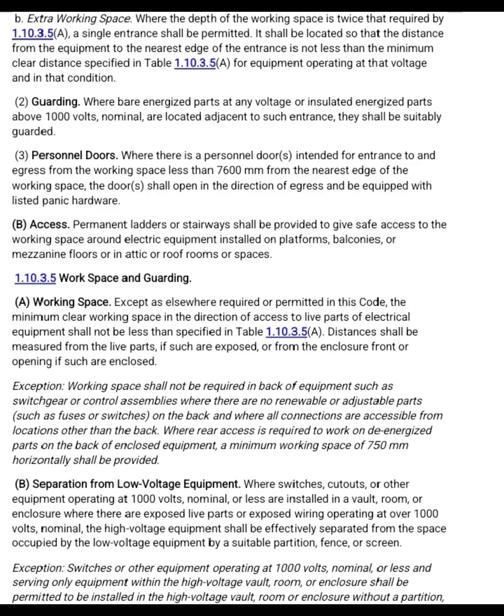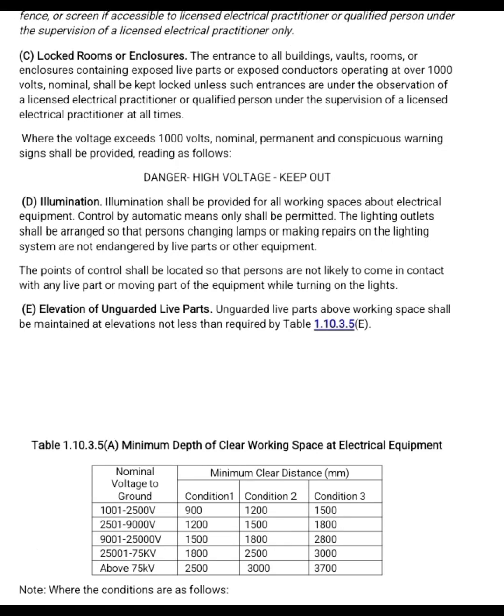This indicates that for extra working space, if the working space is twice the nominal depth, you are allowed to have only one entrance. And in guarding your entrance, if there are bare live parts or insulated live parts above 1000 volts near an entrance, they must be guarded to prevent accidental contact. C. Locked rooms or enclosures. The entrance to all buildings, vaults, rooms, or enclosures containing exposed live parts or exposed conductors operating at over 1000 volts nominal shall be kept locked unless such entrances are under the observation of a licensed electrical practitioner or qualified person under the supervision of a licensed electrical practitioner at all times. Where the voltage exceeds 1000 volts nominal, permanent and conspicuous warning signs shall be provided, reading as follows: Danger, high voltage, keep out.